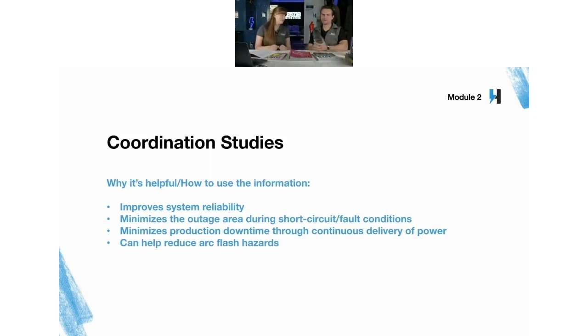If you have any protective device above 1200 amps, according to NEC 240.87B, I believe it is. I'm just throwing that out off the top of my head. What's talked about a lot is coordinating between protective devices. But according to 240.87B, you should actually coordinate devices above 1200 amps with the arcing fault current of the system for arc flash mitigating purposes. Right.